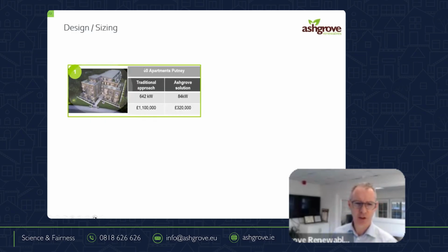So the first project we did was 60 apartments, a relatively small project, but it was sized at 640 kilowatts originally. The cost of that, which actually had stopped the project, was 1.1 million. A gas boiler would have been, I'm going to say, 100 grand by the time all in. But the ground source, if we sized it properly, was actually 84. Now, there'll be raised eyebrows there, but we'll go through the calculations in a second. So this means it's £800,000 less. The project goes ahead, we reach carbon compliance and all the rest of it, but we'll go into the figures of that in a second.